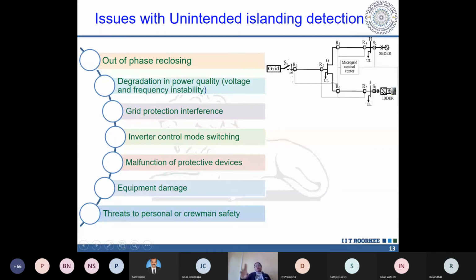In that case, the voltage and frequency of both the grids should remain constant. So this is out of phase reclosing, and degradation of power quality, obviously, because when it is disconnected, there is a change in voltage and frequency. And grid protection interference. Already I discussed with all of you that during the grid connected mode, the current magnitude is something else. During islanded mode, the current magnitude is something else. So the relay settings are going to be changed from time to time. And inverter control mode switching, already I said in the previous slide, because during grid connected mode, the inverter of the renewable sources will take the reference of the voltage and frequency from the grid side. And when the grid is absent, it has to switch over to another control strategy.